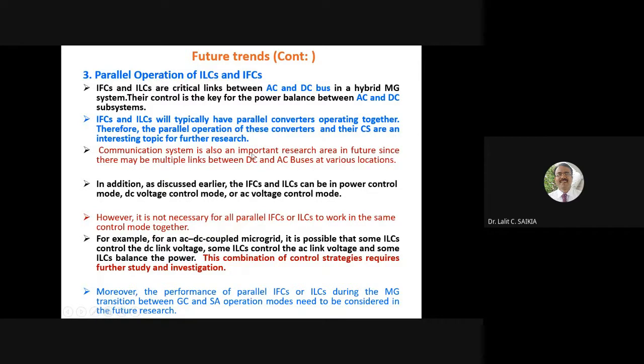Communication systems are also an important research area for the future, since there may be multiple links between DC and AC buses at various locations. As discussed earlier, IFC and ILC can be in power control mode, DC voltage control mode, or AC voltage control mode. However, it is not necessary for all parallel IFC or ILC to work in the same control mode together.